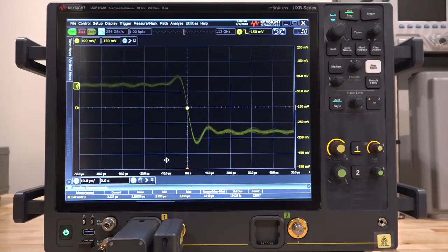So the calibration plane of the calibrator is at the edge of the connector, and the plane of the measurement of the scope is at the connector of the scope itself, and those two are going to match perfectly, and that's how you get NIST calibration on the channel. And it looks amazing. I mean, to get a 3.2 picosecond edge measured live on an oscilloscope, it's never been done before for a real-time oscilloscope.